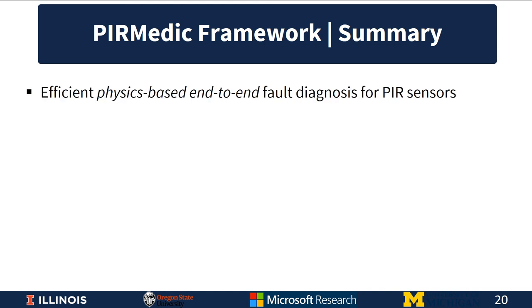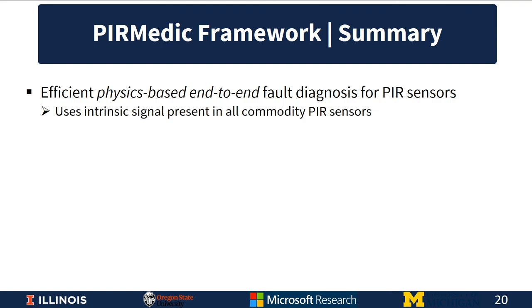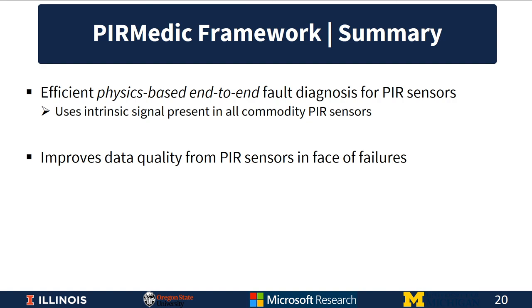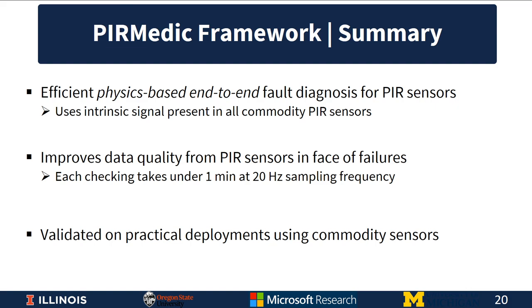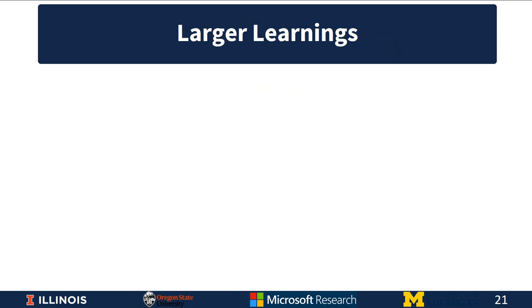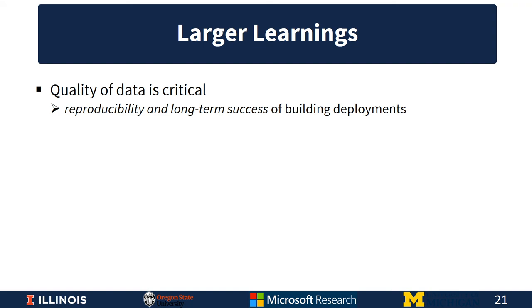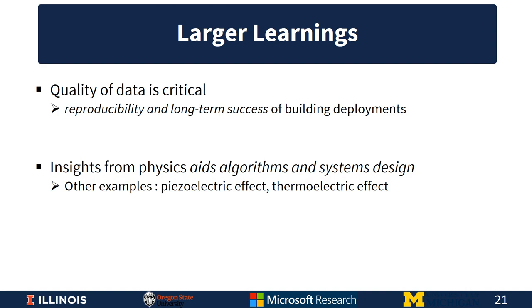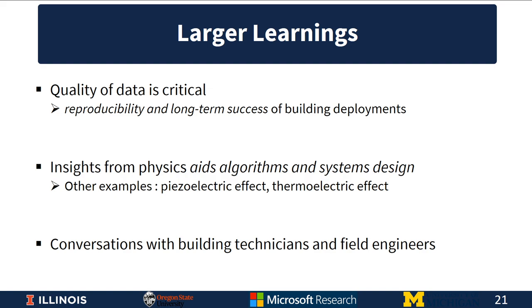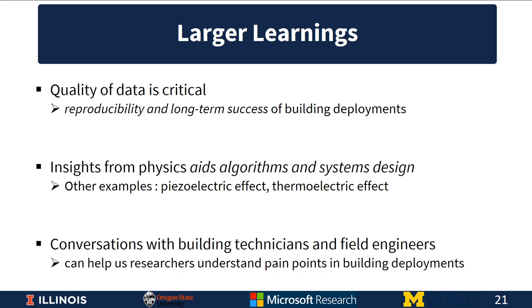In summary, PIRMedic is an efficient physics-based end-to-end fault diagnosis system for PIR sensors that uses an intrinsic signal present in all commodity PIR sensors. Each check takes under one minute at 20 Hz sampling frequency, validated on practical deployments using commodity sensors. Key learnings are that data quality is critical to reproducibility and long-term success of building deployments, physics insights can aid algorithm and system design — as seen with the pyroelectric, piezoelectric, and thermoelectric effects — and conversations with building technicians help researchers understand real pain points.